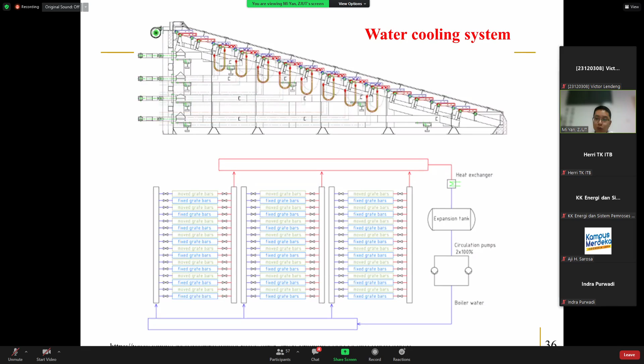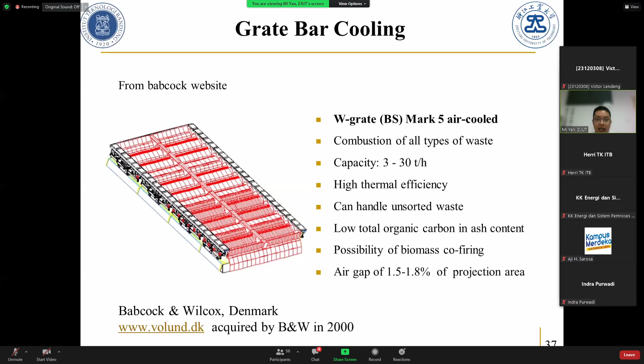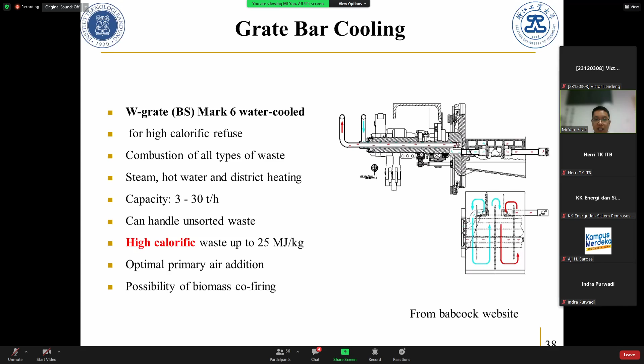This is a company from Denmark. This is air cool. So it has some parameters, and this company also has the water cooling grate. So we call it a Babcock, right? The LHV, or high calorific waste, is up to 25 megajoules per kilogram. So it's possible that for biomass, if the calorific value reduces, you adjust the air excess ratio or optimize primary air additions. So this is the advantage for water cooling.